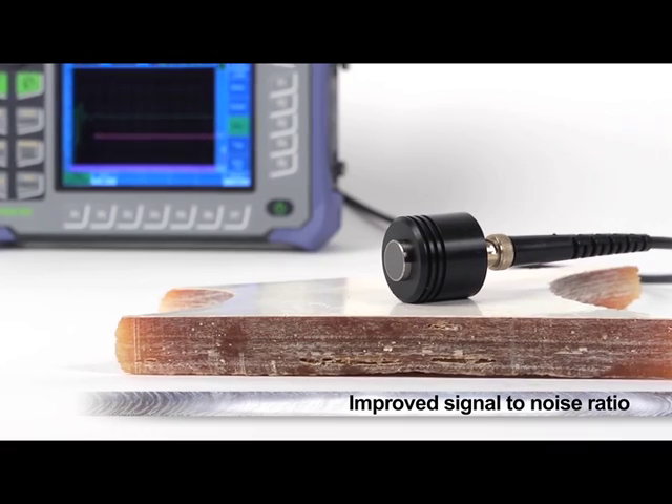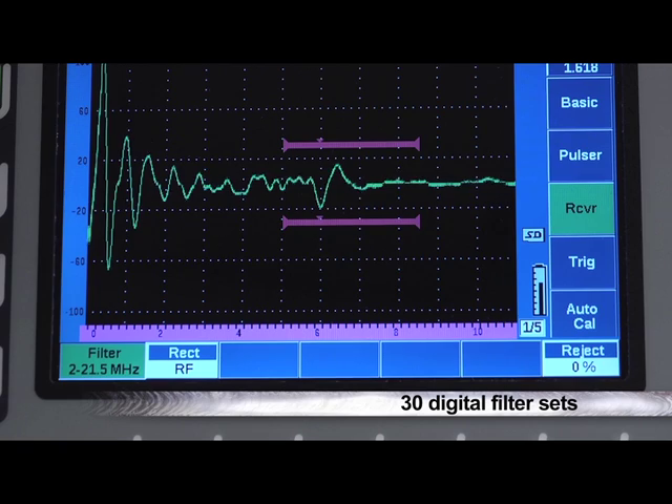Improving the signal-to-noise ratio for inspections on highly scattering or grainy materials is easily managed by the EPOCH 650's receiver filters. The instrument features 30 digital filter sets, all with industry-leading performance and optimized for near-surface resolution.